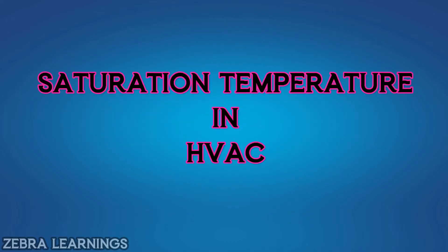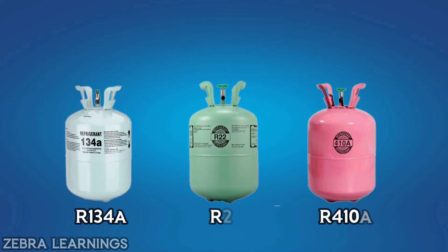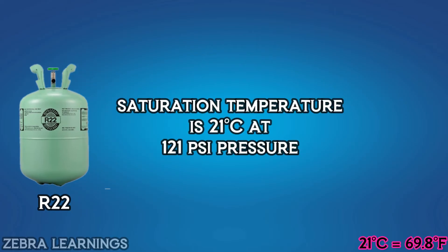Let's understand what saturation temperature is used for in the HVAC system. HVAC systems contain a lot of refrigerants, and each refrigerant has its own saturation temperature. For example, the saturation temperature of R22 refrigerant is 21 degrees Celsius at 121 PSI pressure.